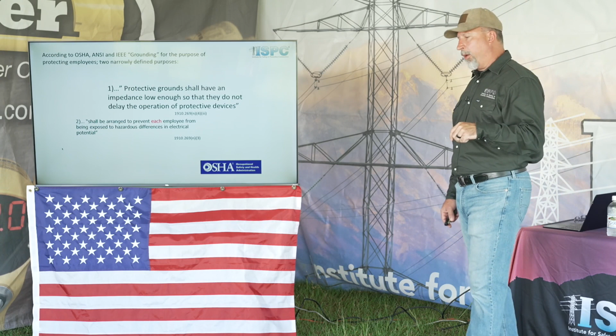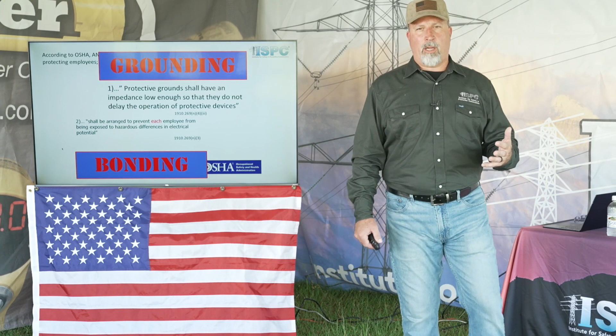Grounding, bonding. We need to differentiate, especially in the substation world. I think the line world does a really good job of equipotential grounding. It's really been kind of rolled out that way in the industry, right? Our information and such, like I said before, is all geared towards the T&D world, the line world when it comes to equipotential grounding. In the substation, not so much, right? And so we need to understand as substation workers, when we ground equipment in a substation, we're not 100% protected. We need to go that extra step, okay?